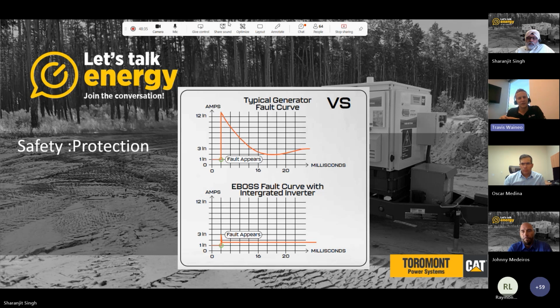So what that allows that inverter to do is detect that output and reduce the output energy so you don't have a large arc flash event downstream of this system, because that inverter is controlling the entire load. So essentially what happens is, in this case, that inverter is going to really reduce the arc flash protection boundary of anything downstream of this hybrid system output.